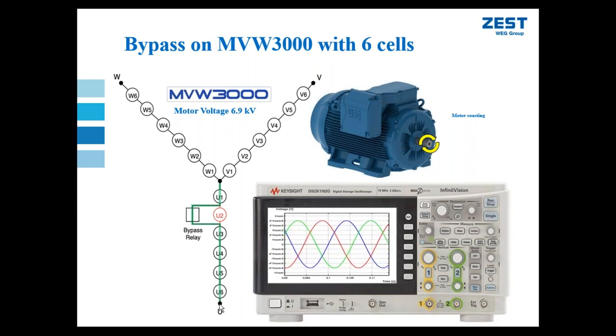Remember, it comes at the cost of reduced efficiency, et cetera, but this is one of the advantages of this topology. You can add a seventh cell, even though you don't need it. That's not going to impact the cost that dramatically. And now you've got proper redundancy. Now, if you lose a cell in any one phase, you can bypass that cell and get 100% voltage. And it makes sense for this topology.